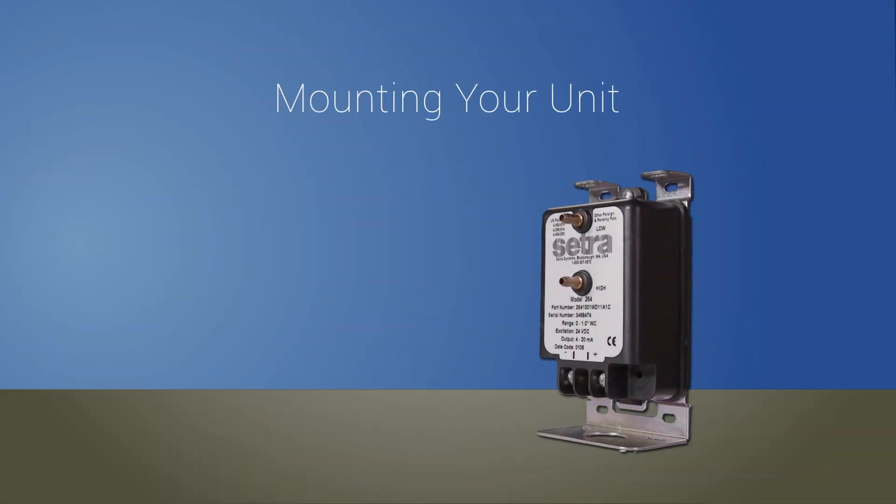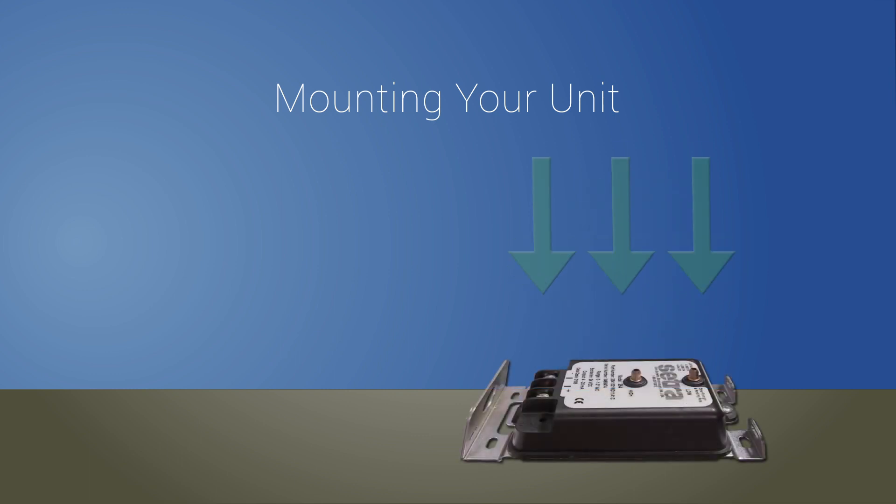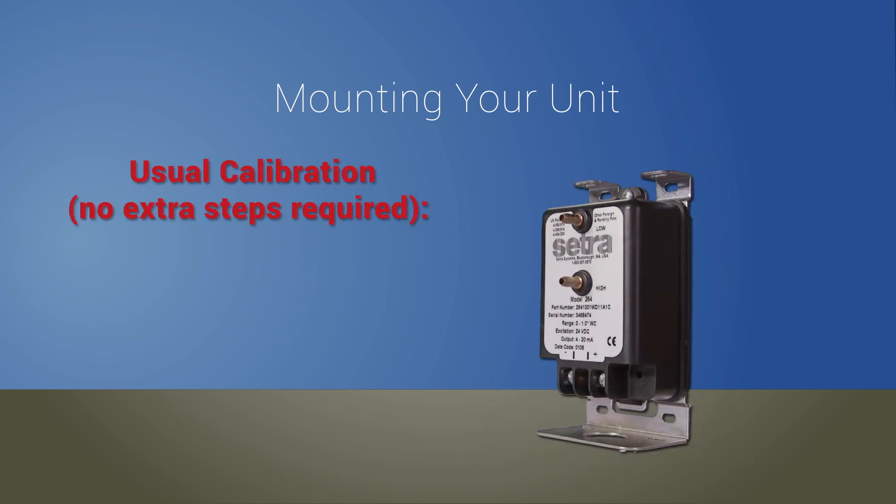The mounting orientation of the unit is also something to be mindful of. Low differential pressure sensors can be affected by gravity if mounted in an orientation that is different than the one they were calibrated in, usually perpendicular.